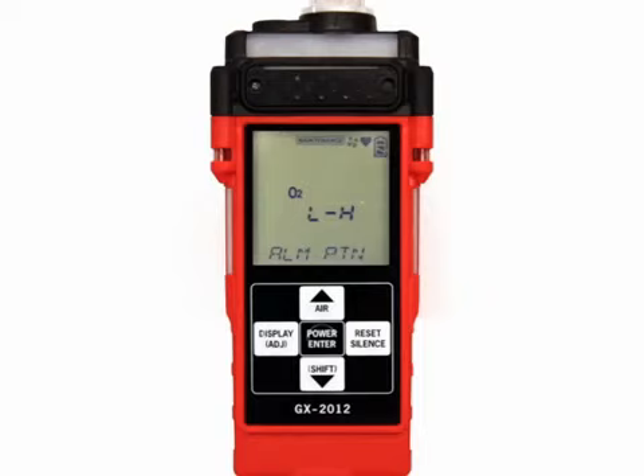The LH pattern provides a decreasing warning and an increasing alarm. The LL pattern provides a decreasing warning and a decreasing alarm. The HH pattern provides an increasing warning and an increasing alarm. This setting is for operation in inert atmospheres and will cause inert to appear along the bottom line of the display during normal operation. Make your selection using the air or shift buttons and press power enter when finished. The factory setting is LH. You may then adjust the warning setting and alarm setting for the oxygen channel using the air or shift buttons. Press power enter when finished with each selection to return to the Alarm Points screen.